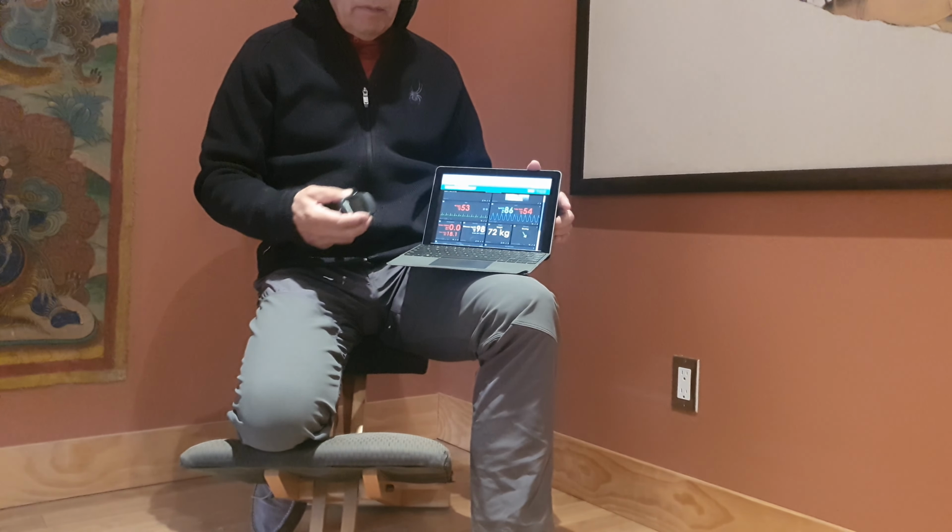But with this device here that I have in my hands, the patient weighs himself. The 4G immediately goes on when he stands on the scale, sends in the piece of data, and disconnects right away. The same thing for a blood pressure, so that we can pick up very stable, very reliable pieces of information from anybody, not requiring them to have a bridge, which is a phone for Bluetooth, not require them to start an app before the device begins to connect to the phone, and then send it over from the phone to the web server.